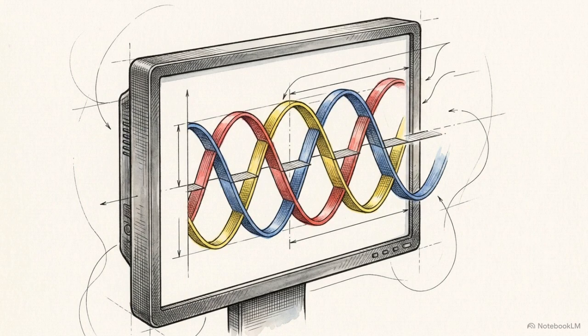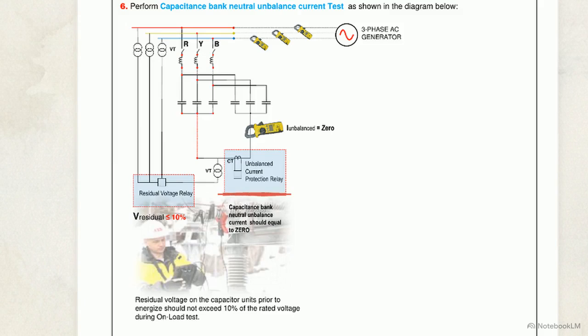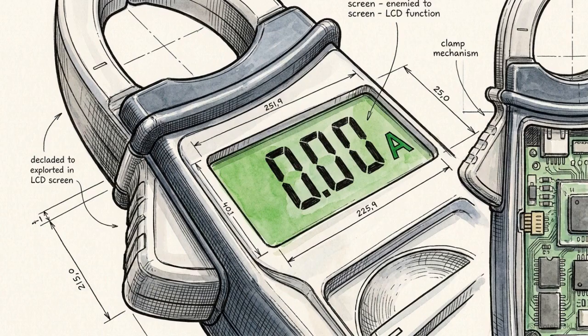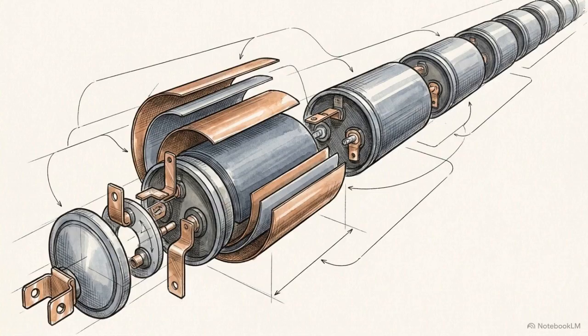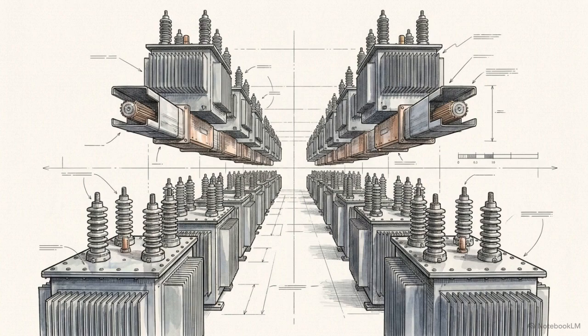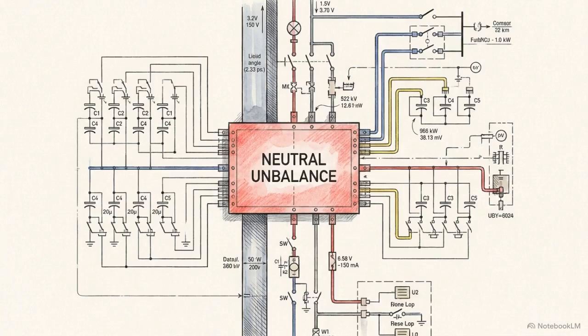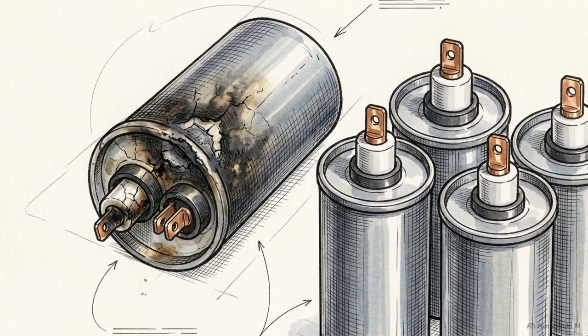The definitive evidence of a healthy bank is found at the neutral CT path. In a perfectly balanced system, the clamp meter reading for unbalanced current should be exactly 0. This 0 reading proves every capacitor element possesses identical impedance, confirming a symmetrical, stable bank. Neutral unbalance is the primary diagnostic for live operations. Any non-zero value indicates an individual unit has degraded and is pulling the system out of balance.